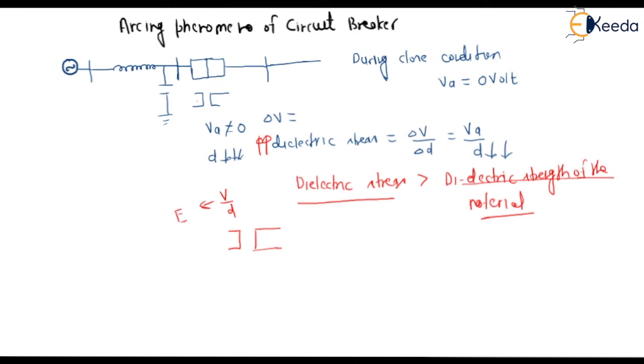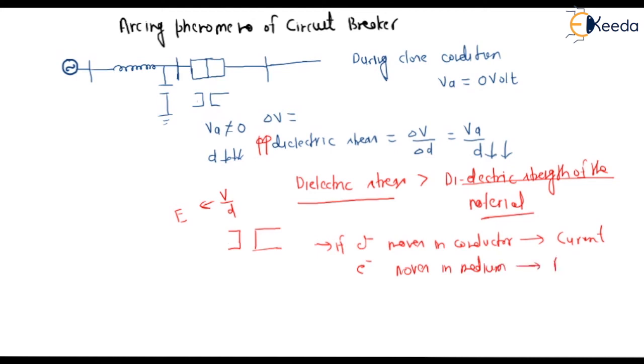When the contact separates, there is a voltage difference between them and there is a distance D. The electric field energizes the electrons here, so when a greater number of electrons are present and moving in the medium, arcing will start. If electrons move in a conductor, that is called current. But when electrons move in a medium, that is called arcing — provided dielectric stress is greater than dielectric strength of the material. This is how arc is initiated in the circuit breaker, due to electric emission theory.